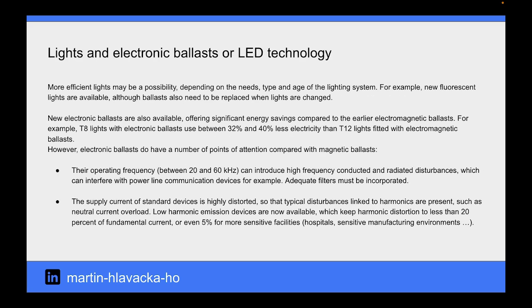More efficient lights may be a possibility depending on the needs, type, and age of the lighting system. For example, new fluorescent lights are available, although ballasts also need to be replaced when lights are changed. New electronic ballasts are also available, offering significant energy savings compared to the earlier electromagnetic ballasts. For example, T8 lights with electronic ballasts use between 32% and 40% less electricity than T12 lights fitted with electromagnetic ballasts. However, electronic ballasts do have many points of attention compared with magnetic ballasts.